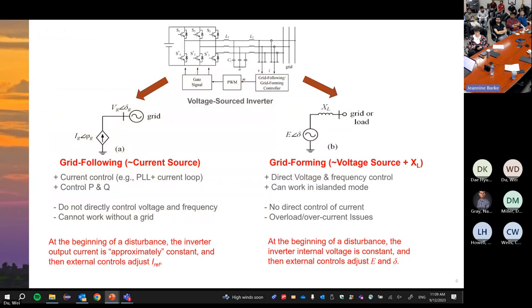Here is some background information. Renewables and batteries connect to the system through the voltage-source inverter. Today's inverter hardware is the same — they always use a voltage-sourced inverter — but the control strategy makes their dynamic behavior totally different. There are two main types of controls. One is called grid-following, and another is called grid-forming. Today, maybe more than 99% of grid-connected inverters use the grid-following control strategy. They rely on the system providing a strong grid voltage, and the inverter regulates the current injected into the system, typically using a phase-locked loop and current loop. It does not directly regulate voltage and frequency, and must be connected to a strong grid.